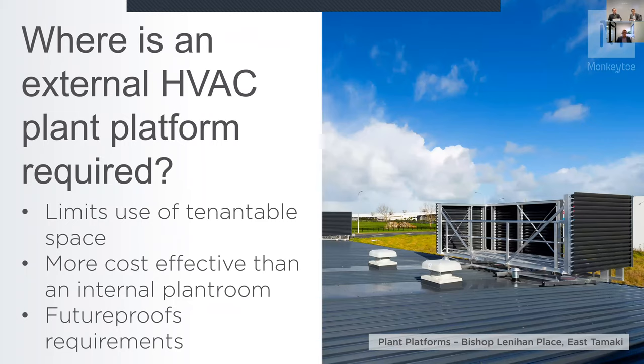Where is an external HVAC plant platform required? Key things: it limits the use of rentable space, it's a more cost-effective option than an internal plant room, and it future-proofs the requirements for supporting equipment. A plant platform on the roof costs a fraction of what it costs to have an internal plant platform, where the standard equipment square metre rate is obviously a lot higher when it's internal.